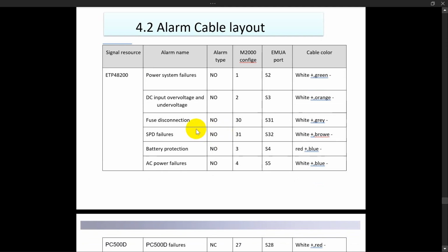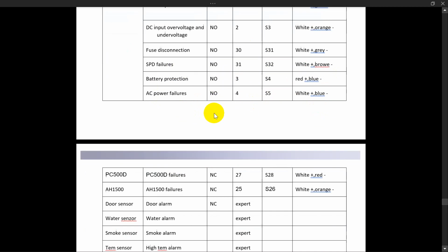For any rectifier, it also has sensors for alarms. So for power alarms, there are sensors shown here for this type, ETP48200. It's also up to the sub rack used in your site according to your operator specification. So here we have power system failure, DC alarm, fuse disconnect, SPD failures, battery protection, AC power failures, according to the color code for each cable and each alarm. And here this is the EMUA port. As discussed, this changes from one operator to another.